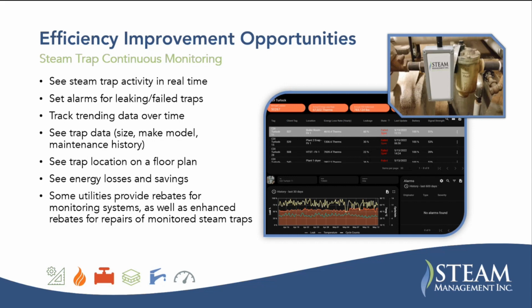They're all different. Traditionally they were wired, and so the cost was pretty high for that because you're having to run wiring throughout your whole distribution system to catch all these traps, right? Now they're usually wireless. They can be Wi-Fi based or LoRaWAN based, or through a cell signal. The ones that we typically use use a cell signal through gateways, and they communicate to the cloud that way. Jamie, you have any more comments on that?